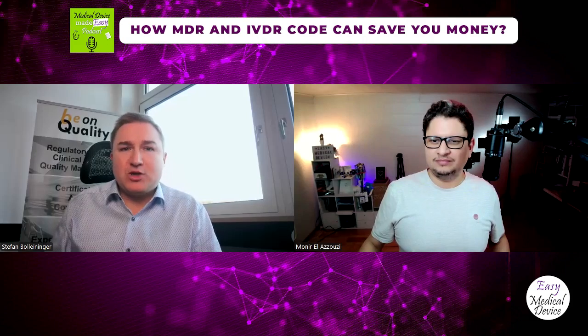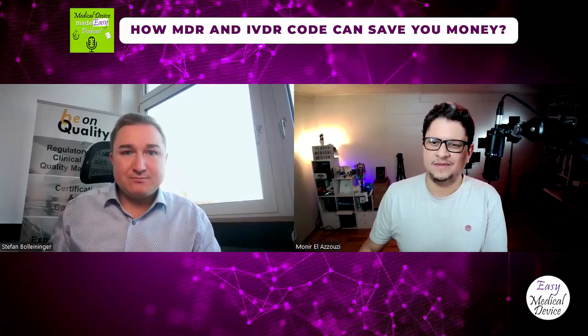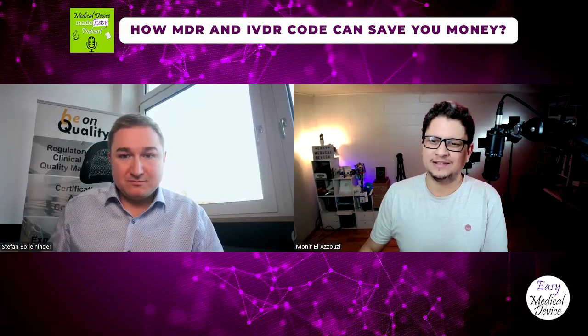No, that's something you can do. You add the product to the product list, then you request a certification change, to change the certificate, they see that everything is fulfilled that you need to do, and then they add it on the certificate. No technical file change, no technical file assessment, no audit needed. For class 2A currently, let's just speak about class 2A.